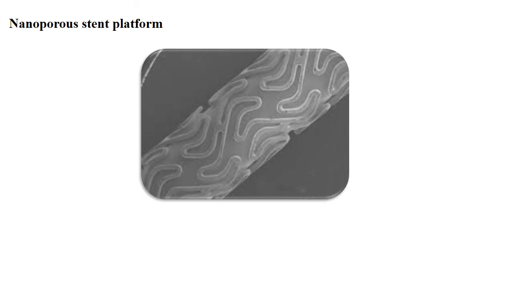The last type is the nanoporous stent platform. By reducing the pore size to the nanoscale, properties of drug delivery are enhanced and the surface nanotopology is altered, providing more effective drug delivery devices. Micro and nanopores act as a reservoir so that multiple drugs can be loaded, which leads to the development of polymer-free stents — allowing us to avoid the side effects associated with the presence of a polymer.